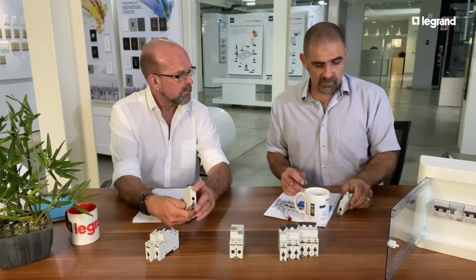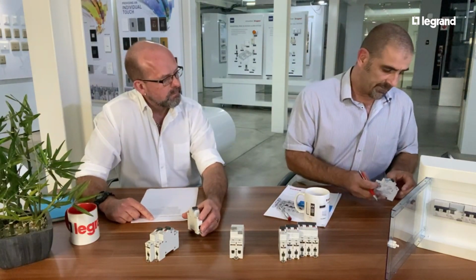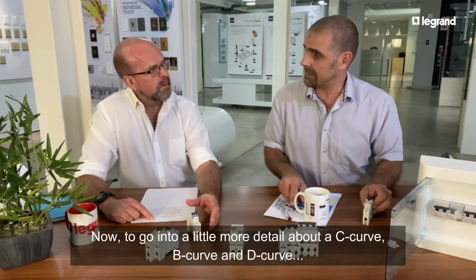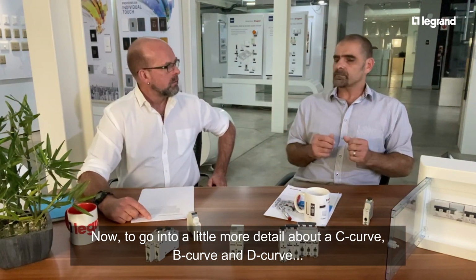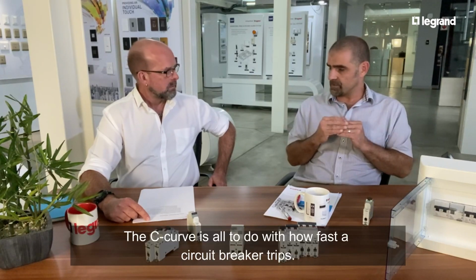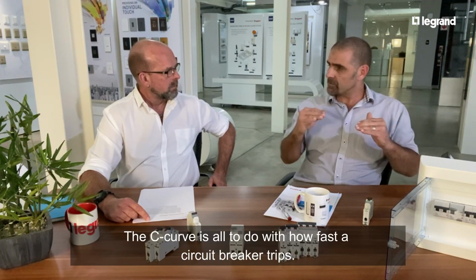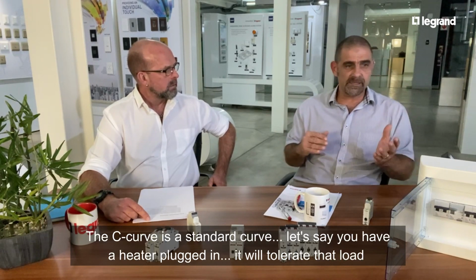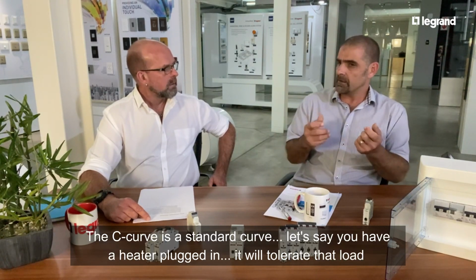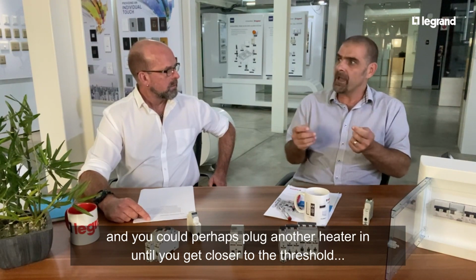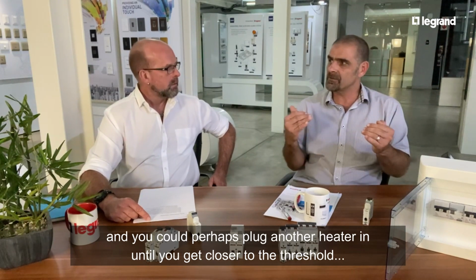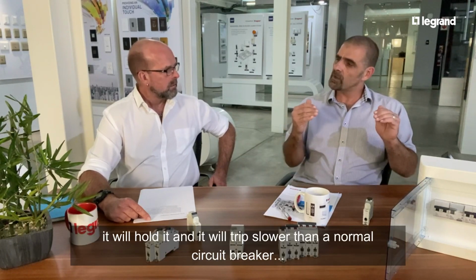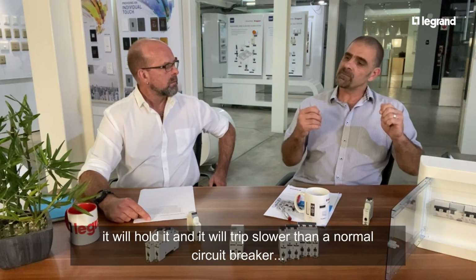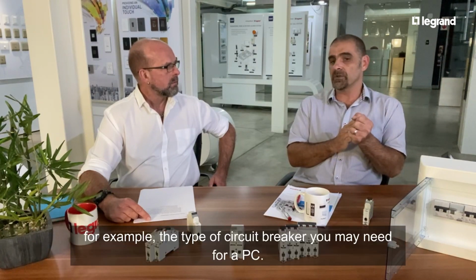Now, if I go into a little bit more detail on the C curve, B curve, and D curve, what does that mean? It's all to do with how fast the circuit breaker trips. The C curve is a standard curve, which, for example, if you've got a heater plugged in, will tolerate that load, and you can perhaps plug another heater in until you get closer to your threshold and your limit. It will hold it, and it will trip slower than a normal circuit breaker, for example, that you'd require for a PC.